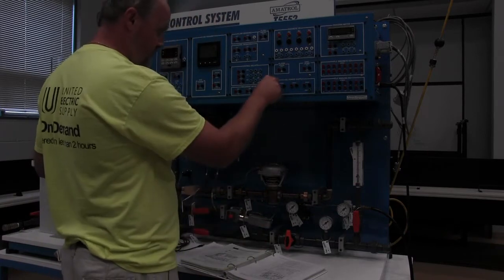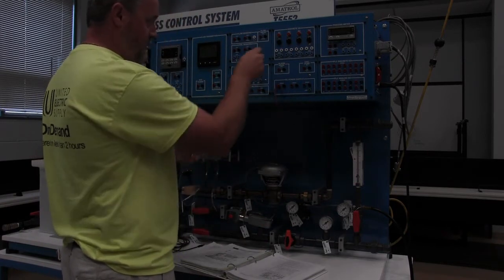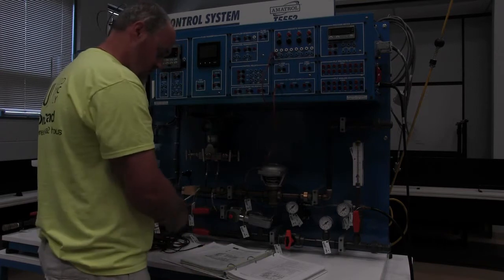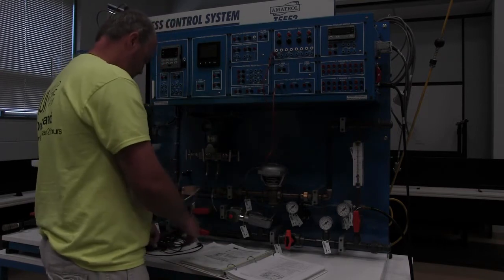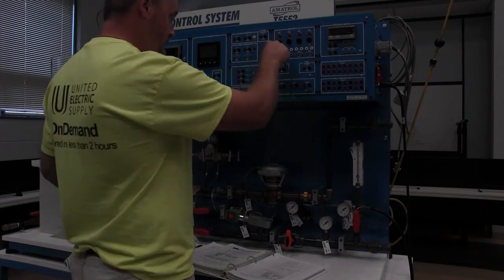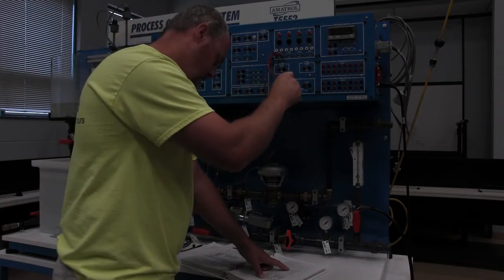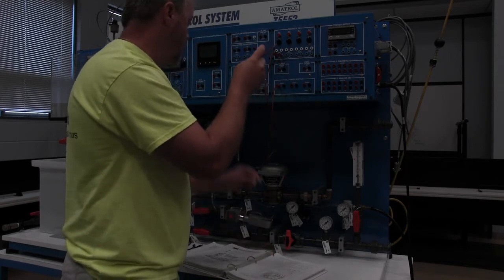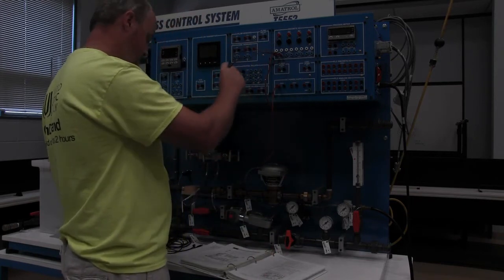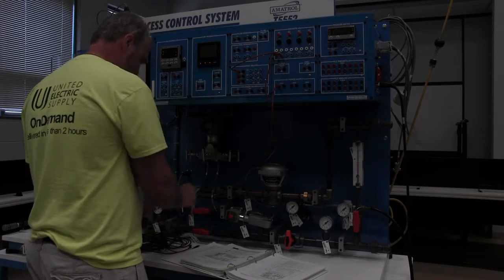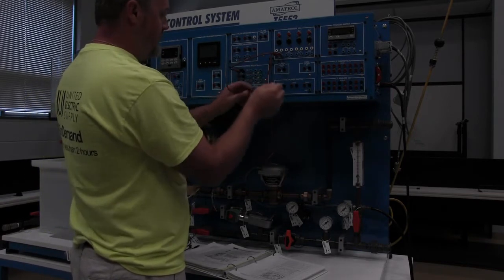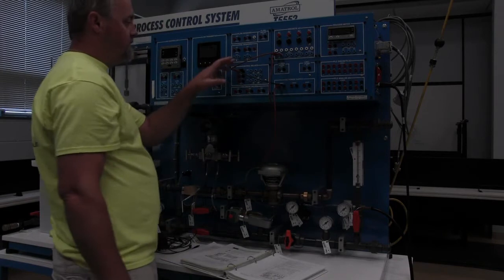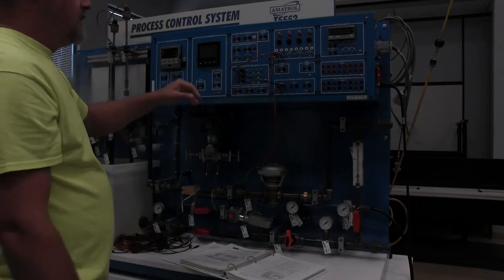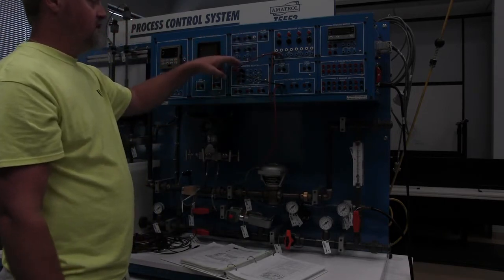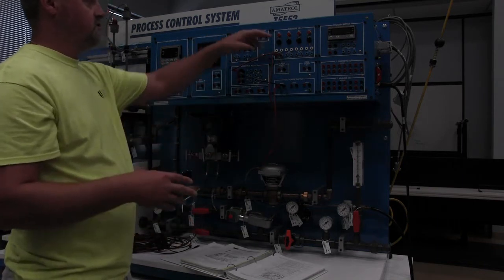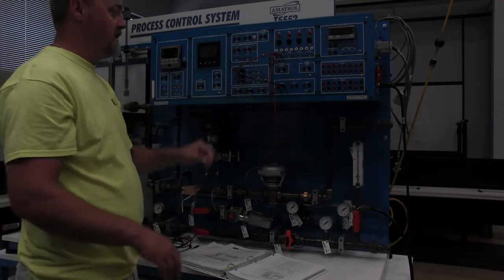So we're going to come off of 24 volt power. We're going to go to selector switch 1. We're going to come off of the other side of selector switch 1 and go to control relay 1, CR1, the coil of it. We're going to come off of the other side of the coil and go to a negative. So this is the coil of a relay, is all it is. When this switch is on, this relay is going to be energized. When this switch is off, this relay is going to be de-energized.